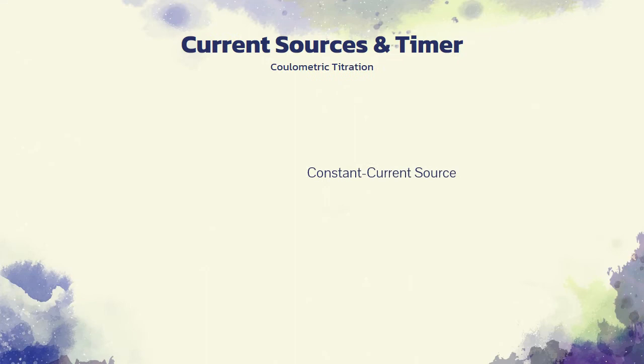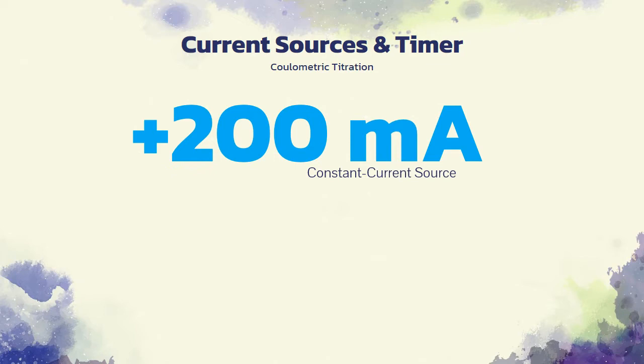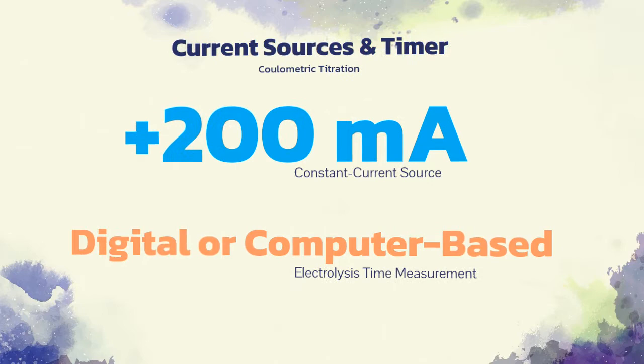The constant current source for a coulometric titration is an electronic device capable of maintaining a current of 200 mA or more that is constant to a few hundredths percent. Such constant current sources are available from several instrument manufacturers. The electrolysis time can be measured very accurately with a digital timer or a computer-based timing system.